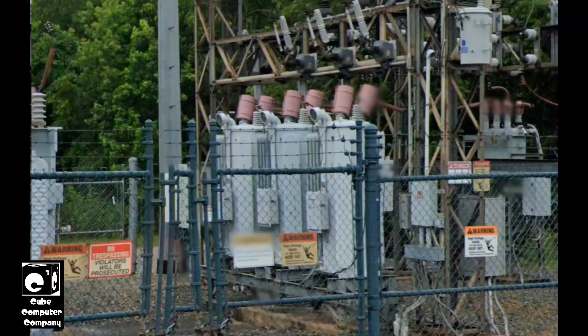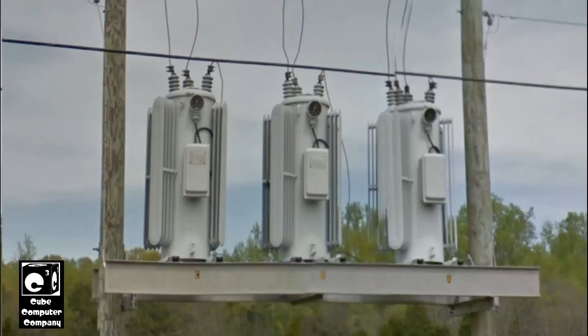Regulators perform an essential function. They're typically found in substations and are also sometimes found out on the distribution feeder many miles away. As demand on the system changes — for example on a cold winter morning there's a lot of demand from heat running and everybody cooking breakfast, getting ready for work or school — then in the afternoon things calm down, and in the evening demand goes up again as everyone cooks supper.